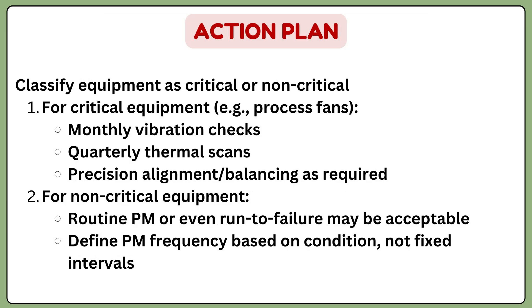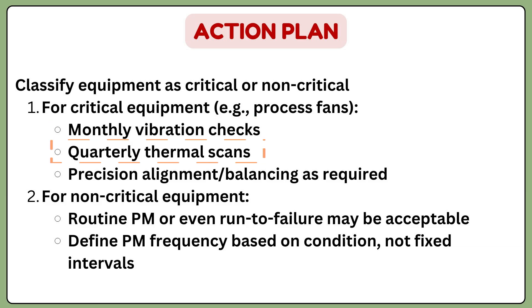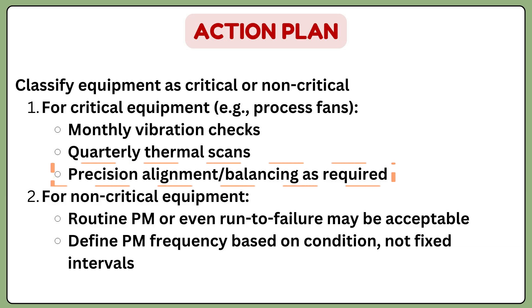The seventh question leads to the action plan — what can be done to prevent such failures. For critical equipment, this could include monthly vibration checks, quarterly thermal scans of the electrical panel, and scheduled preventive maintenance such as precision balancing or precision alignment. Depending on the type of failure, a targeted action plan is created for that particular equipment.